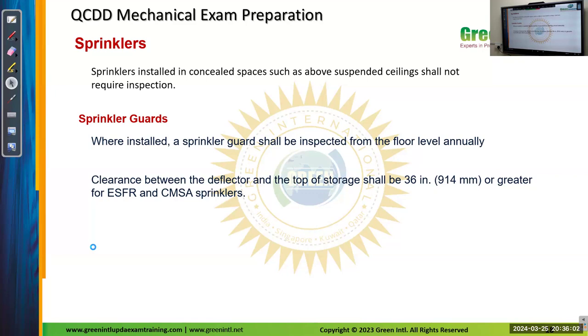It means if you have clearance between the deflector and it is installed in a top position, it is not required for you to climb up there to inspect it. That is the sprinkler guard. If you can inspect from floor level itself, it's a visual inspection, okay, not the functionality of the sprinkler.